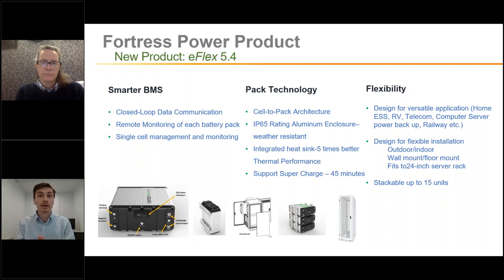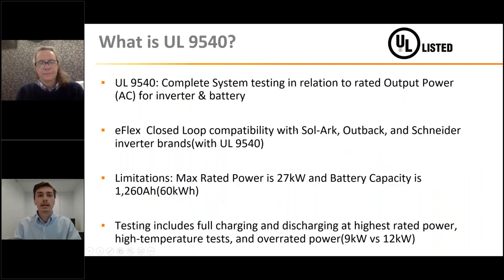So we have these two options, and depending on what your project calls for, you can use one or the other to fulfill your customer's requirements. The eVault has UL1642, and the eFlex has UL1973 and UL9540. UL1642 covers the cells themselves in the battery. UL1973 is the entire battery pack being UL listed. UL9540 is complete system testing in relation to rated output power and AC unit for the inverter and battery.